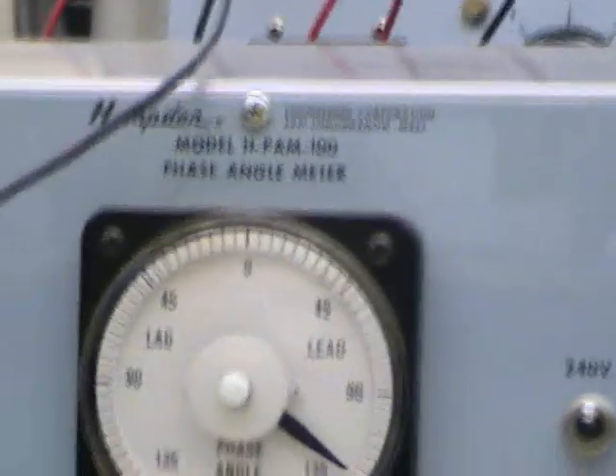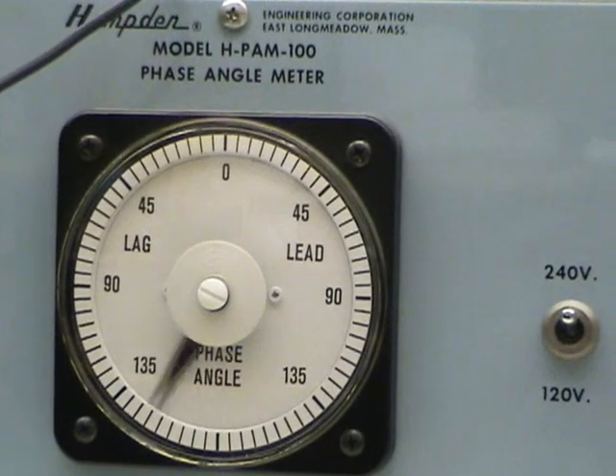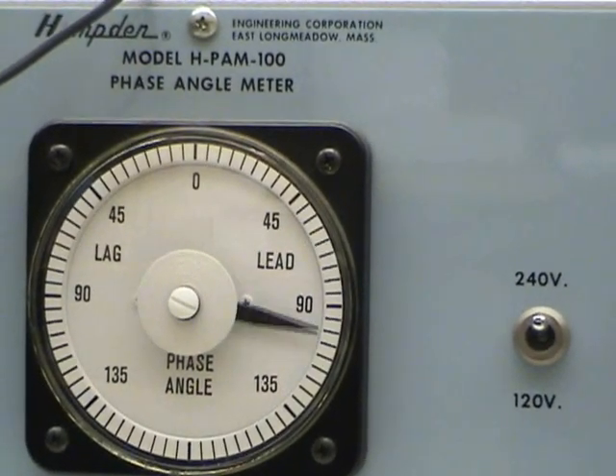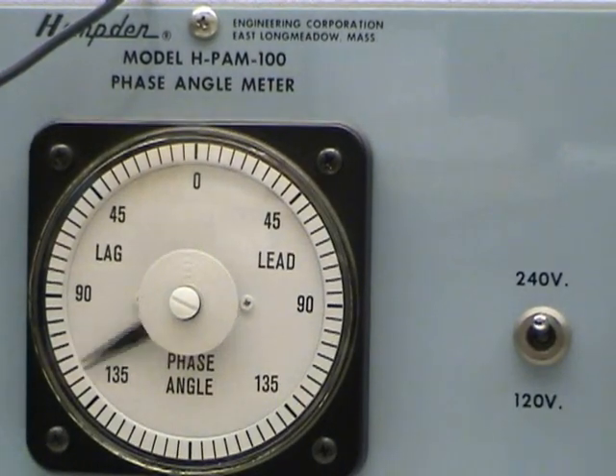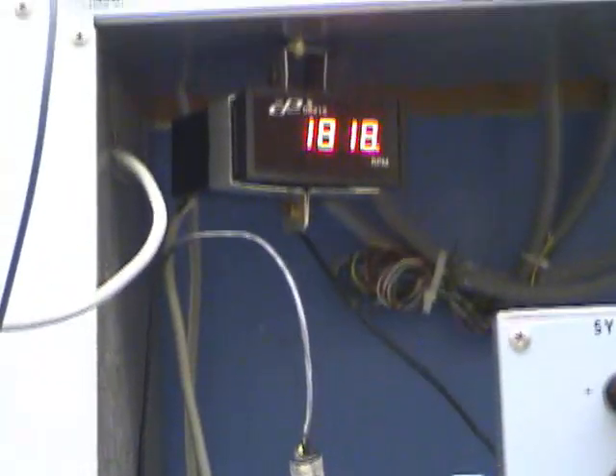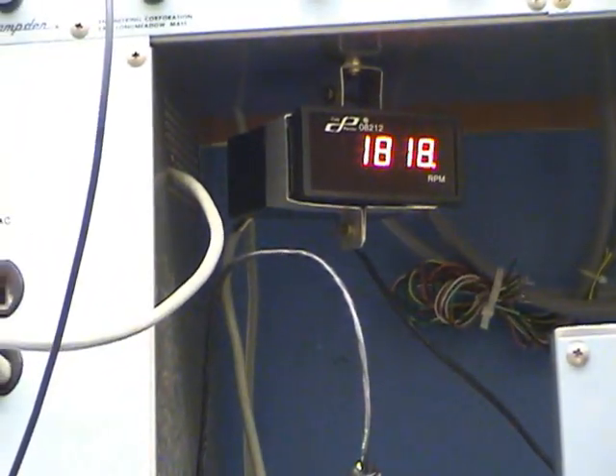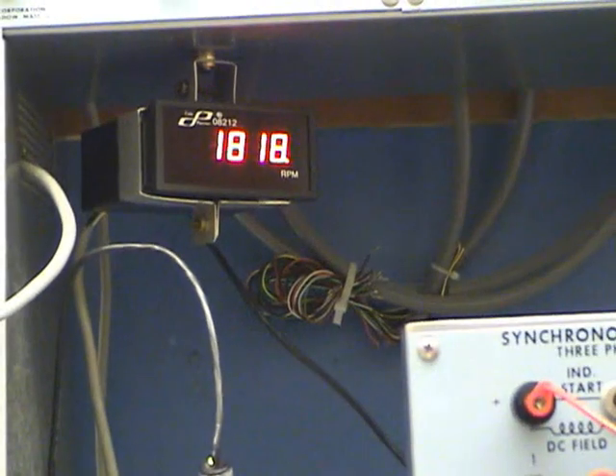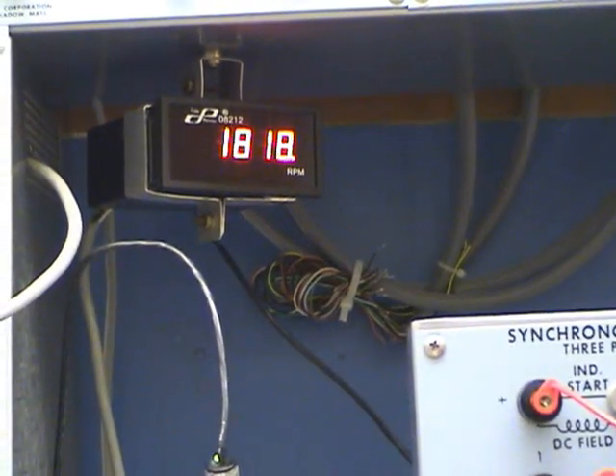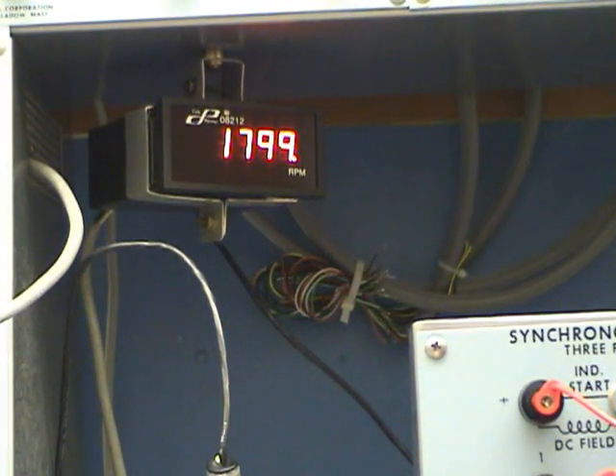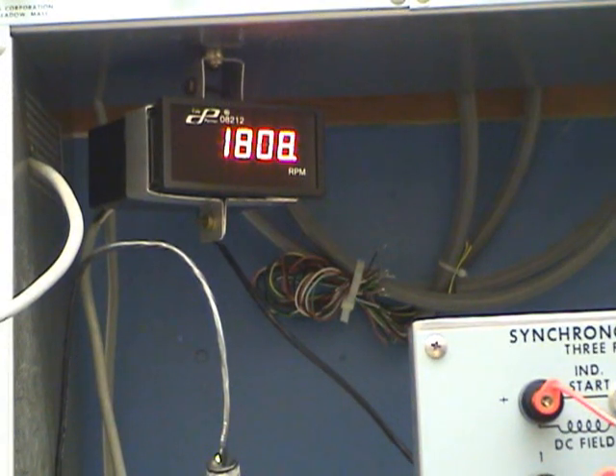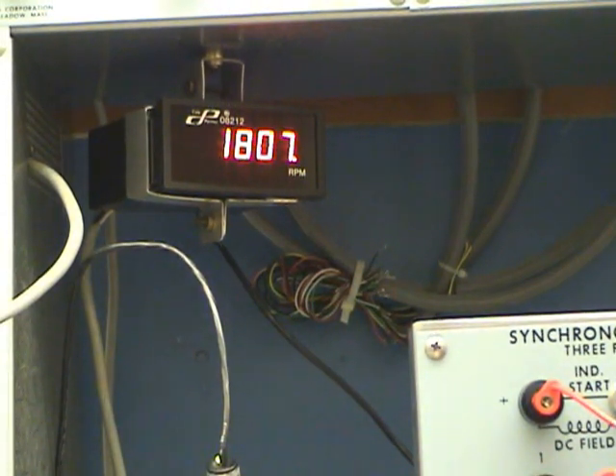Looking at our phase angle meter, we can see that the phase angle meter is continually revolving, indicating a difference in speed. It is also rotating toward the machine, and so that indicates the machine is running a little high, and that is in fact the case here. If we look at our tachometer, we're at about 1818 RPM. So I'll try to bring that speed down just a little bit. A little bit above 1800 RPM.